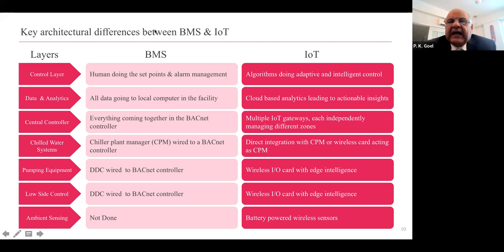The other thing is, suddenly in a 10-storied building you are getting complaints from one floor - somebody says high temperature, somebody says low temperature. With the BMS, what will you do with it? You have to go with a stick and open more dampers, close more dampers. Now you can go plug 15 wireless sensors on that particular floor for the next 7 days, and you can trend them, and see who feels comfortable at what temperature. Those kinds of possibilities are much more there.